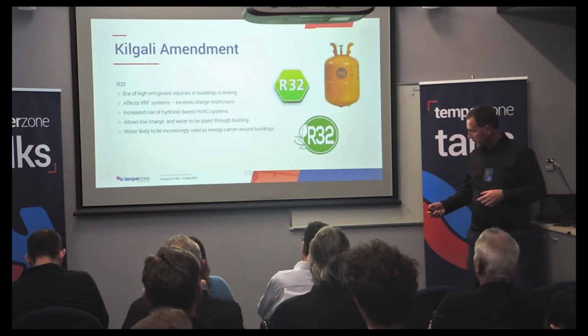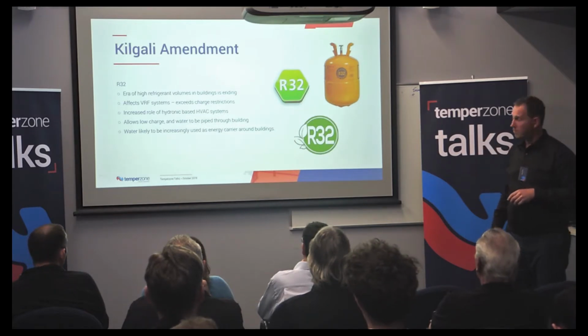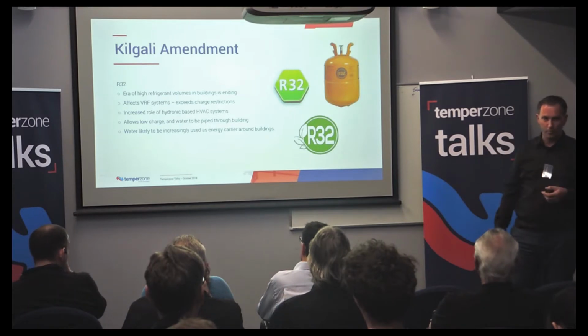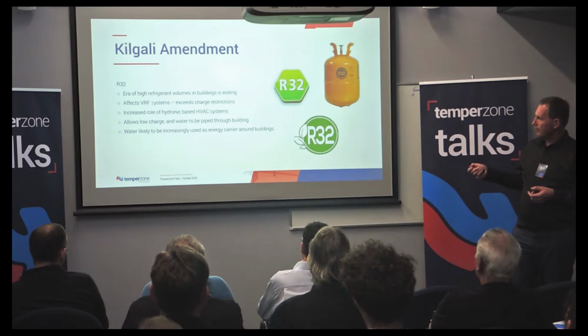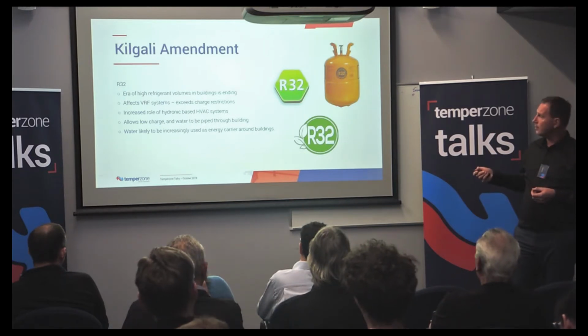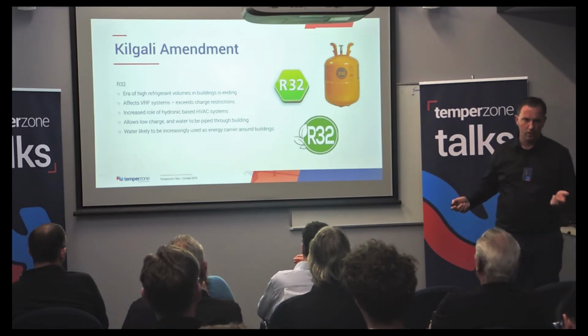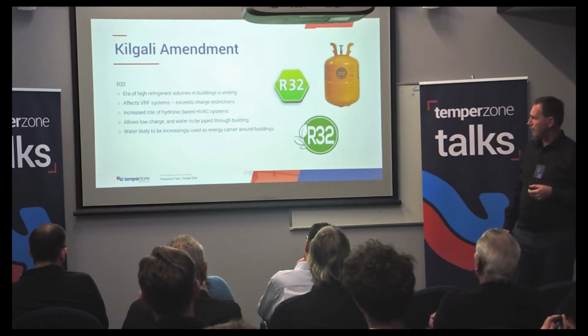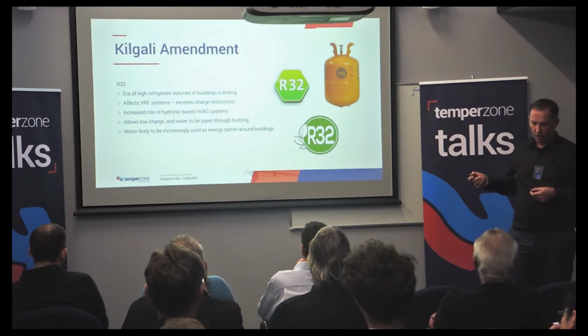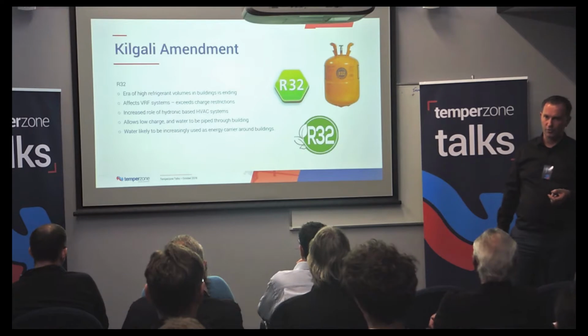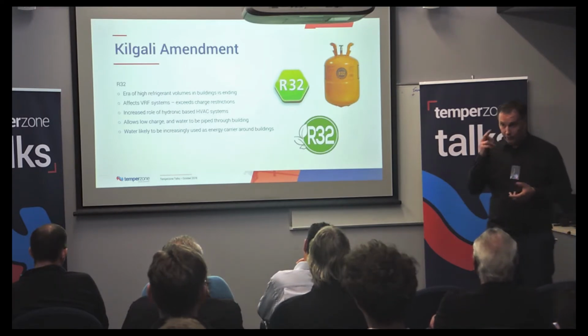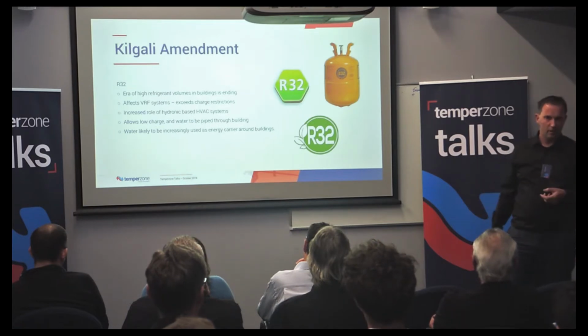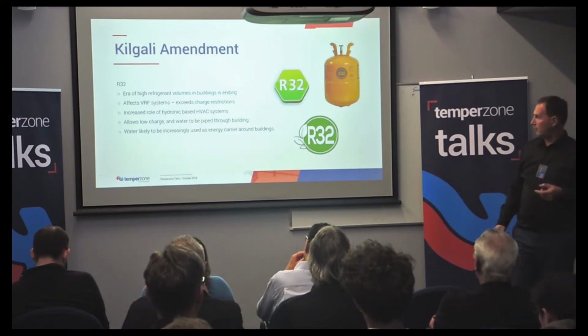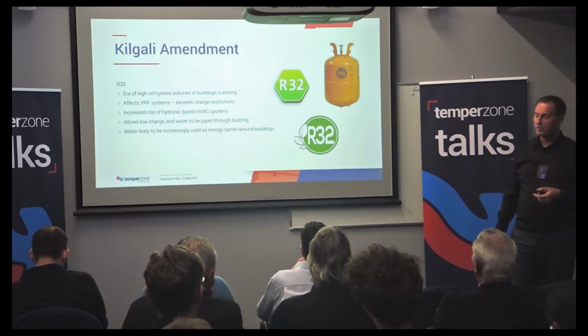So just looking at it more broadly, it's been very much marketed as green. It's not incredibly green, but it's a heck of a lot better than where we've come from. It really is affecting VRF systems, and we see an increased role of hydronics as a consequence of this. The advantage of hydronics is you have a very low charge, because you're not pumping refrigerant around. So rather than having 100 kilograms for a 50 kilowatt cooling system, you might only have 6 kilograms. So not only do we get the GWP reduced by a lot, we can also use much less refrigerant for the same kilowatt cooling by changing the format of air conditioning systems.